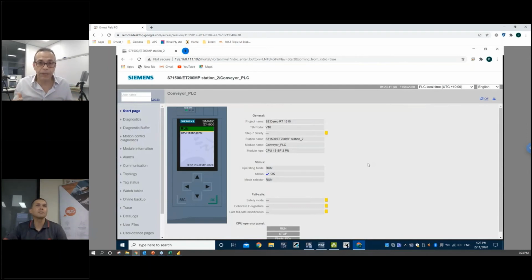You create the PLC on TIA Portal, and you just go to the settings and you tick a couple of boxes. That's it. Now, obviously, we don't want people to hack into our equipment. And every time you open a web browser, you definitely open the door to hackers. So what we do is we give people the option of having hierarchies of login and passwords and limitations. So some people can have just read-only, some read and write. In this particular case, I give you no login at all, so you can just go in. We make it as easy as possible because we're training. This is the right environment for that.